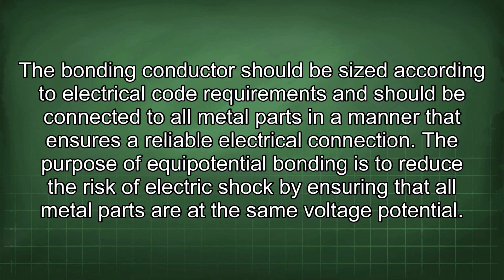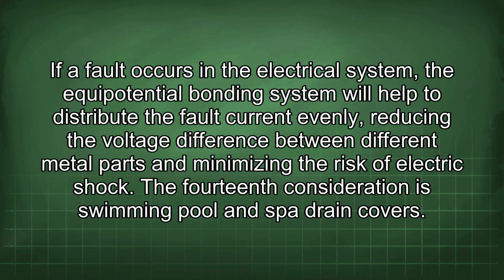The purpose of equipotential bonding is to reduce the risk of electric shock by ensuring that all metal parts are at the same voltage potential. If a fault occurs in the electrical system, the equipotential bonding system will help to distribute the fault current evenly, reducing the voltage difference between different metal parts and minimizing the risk of electric shock.